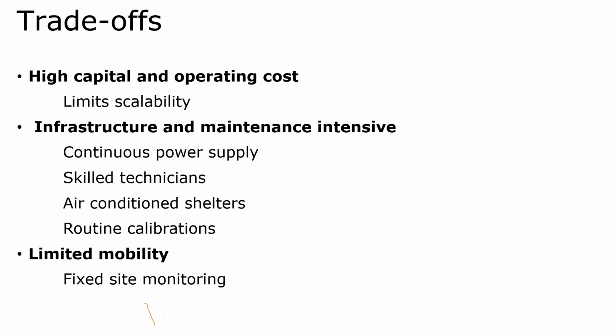At the same time, we need regular calibration. The calibration can be a flow calibration, a span calibration, a photo detector calibration. There can be so many calibrations involved. And they are infrastructure and maintenance intensive. Why do I say maintenance intensive on infrastructure? Because you have seen in the earlier slide that it requires a shelter. To construct such a shelter, we need space. We also need unobstructed space, because we need a free flow of air so that the measurement is not biased. We need continuous power supply, not only for the instruments but also for the air conditioners. At the same time, we need conditioned power, without leakages and with proper earthing. Otherwise, the instruments can go bad.